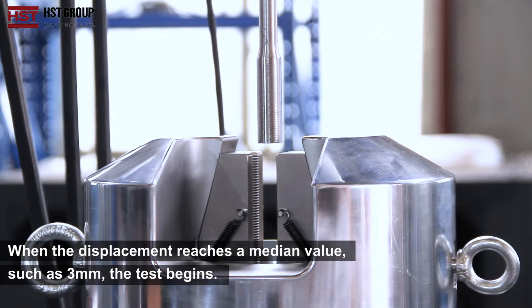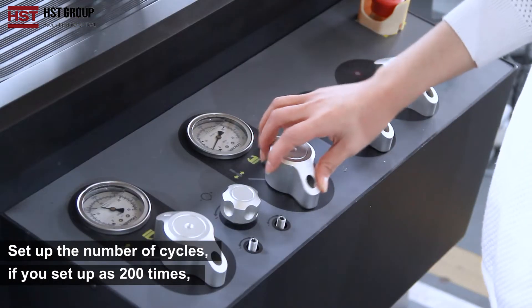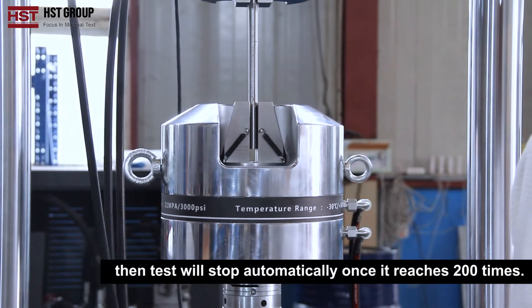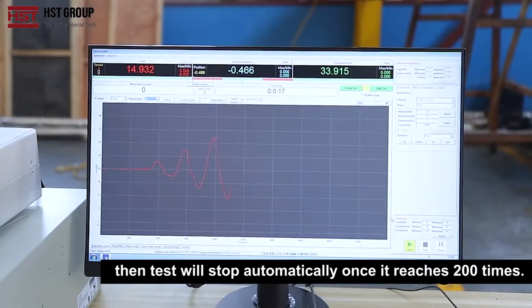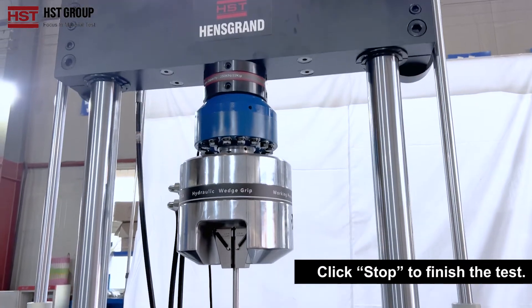When the displacement reaches a median value such as 3 mm, the test begins. Set up the number of cycles — if you set 200 cycles, the test will stop automatically once it reaches 200 cycles. This method is optional to set or not. Click stop to finish the test.